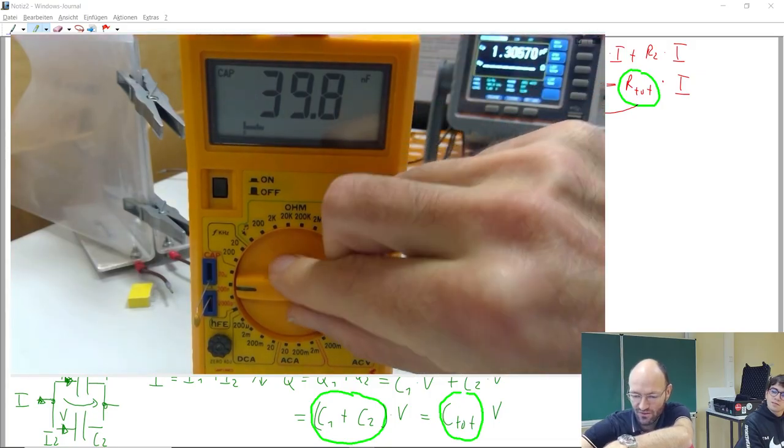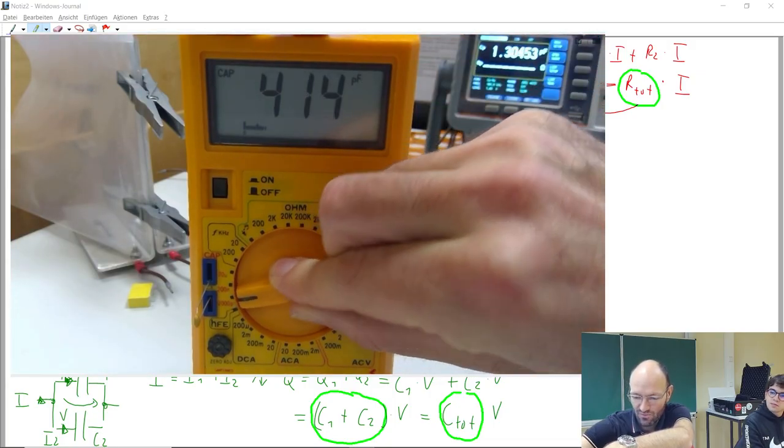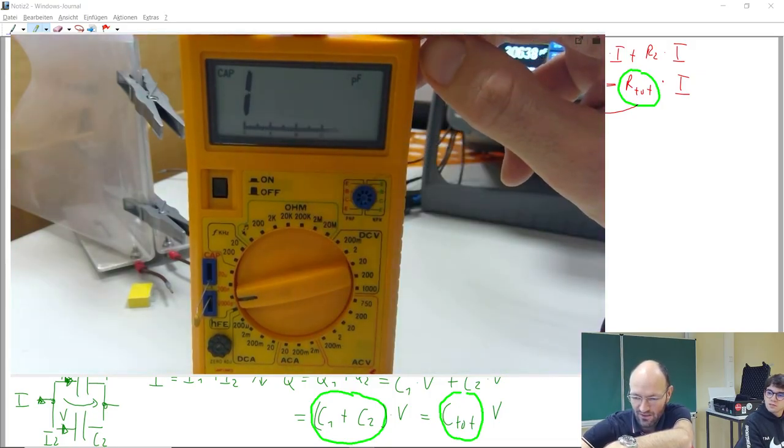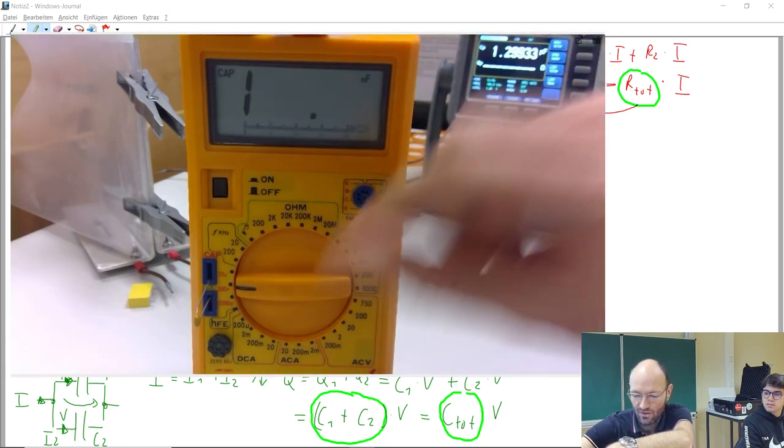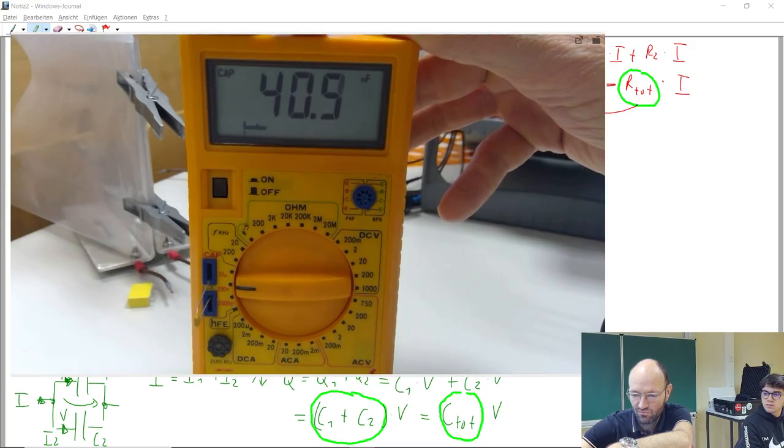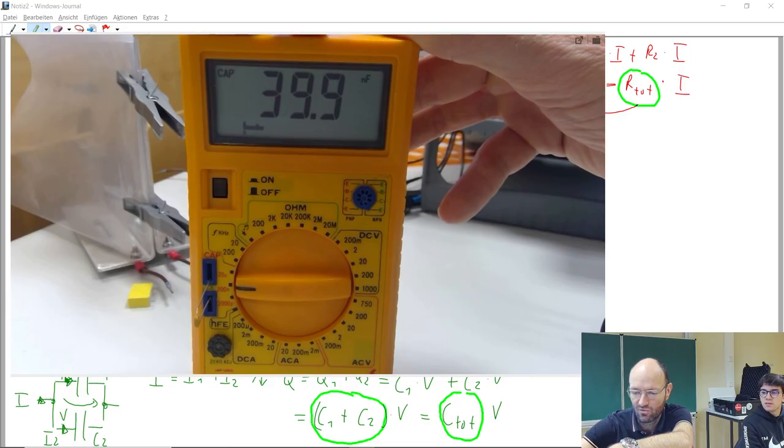We get 39.8 nanofarad. Not 47. And so if we go into this picofarad range, then we have overload, it's too much. So in this range, this looks meaningful. We get something like around 40, 39.9, something like this.